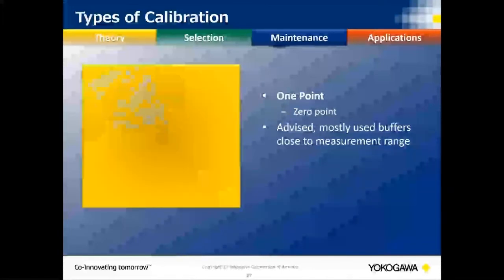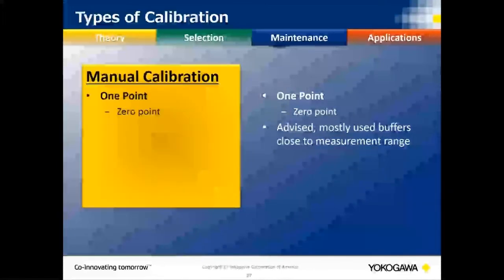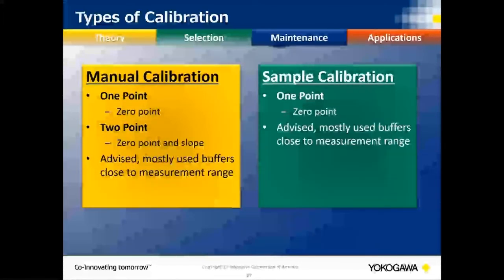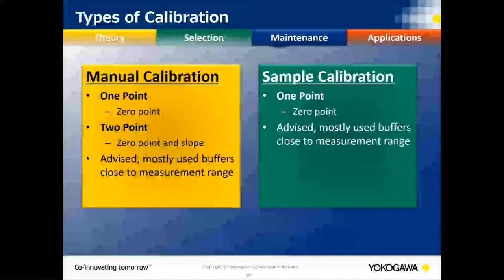There are two types of calibration: manual calibration, either a one-point (zero) or a two-point (zero and slope). Traditionally, because it's just a platinum measuring pen, there's no pH glass aging to compensate for, so we do a one-point manual calibration. You can do a grab sample calibration, but pick a solution close to your process ORP value.